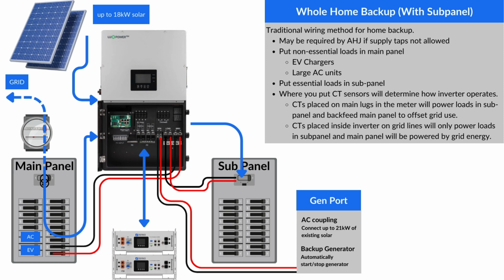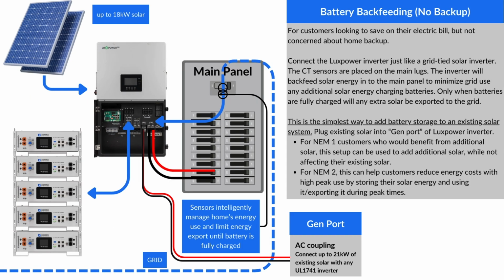So that setup with the CT sensors on the main lugs and using a subpanel is another way of load shedding in the event of a grid outage, meaning that grid goes down, the main panel is going to be de-energized, and the sub panel is going to continue to get powered by the inverter. And ultimately, this may be the only way to permit this system with some AHJs in cities. This diagram is showing another way to use battery systems for homes that aren't concerned about whole home backup. They're really concerned about still taking advantage of self-consumption and trying to minimize energy they're using from the grid to reduce their electric bill.